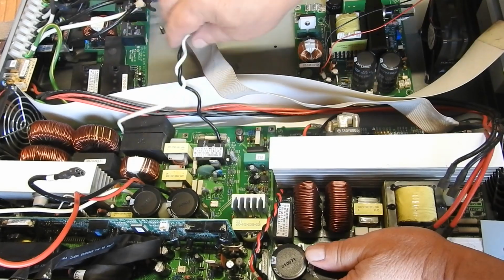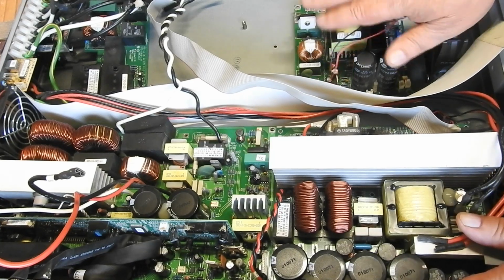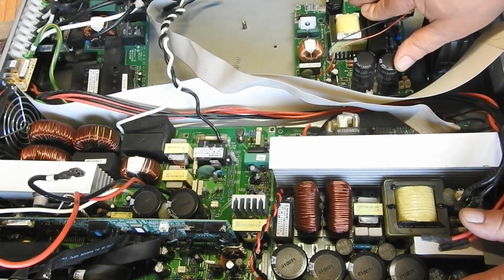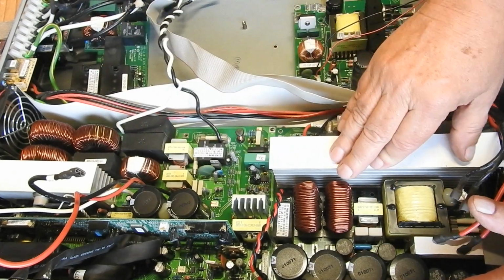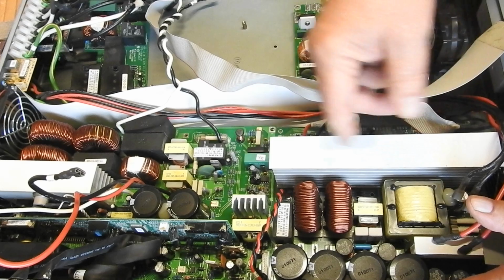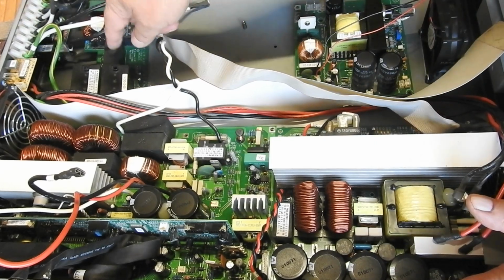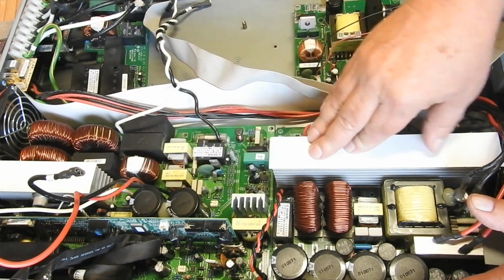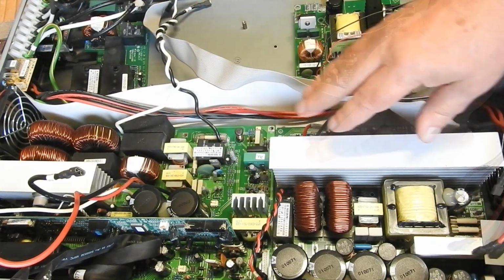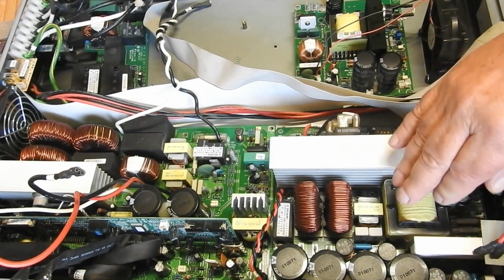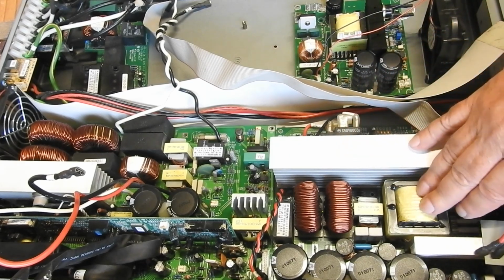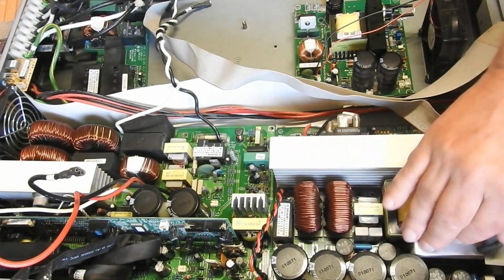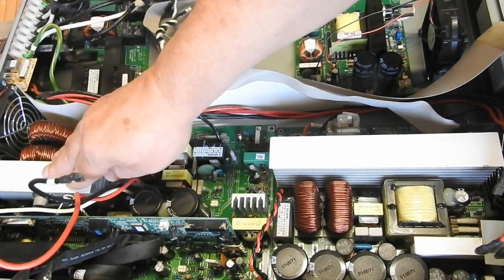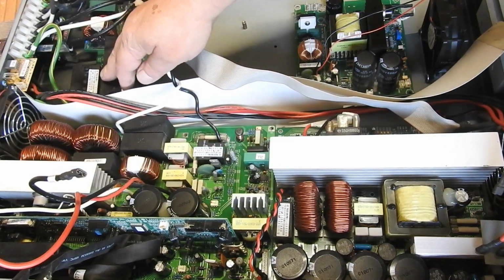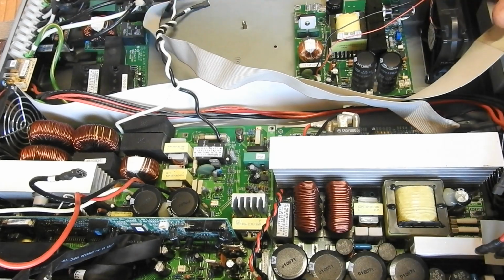From what I can tell, the basic layout is this: this board here is for charging the battery, and these 3 boards are part of the path both in and out. It comes in here, goes into this board, then into here, then to here where it's power factor corrected and rectified, then turned into AC to go to this transformer where it begins its return journey, going back through more rectifiers and filtering, going into here where it's inverted, then it goes back into here and to the output terminals. Let's have a look at each of these bits a bit more closely.